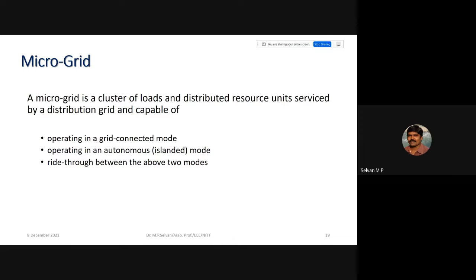A microgrid should be capable of operating in grid connected mode and in isolated or autonomous mode. If this capability is not there for the distributed resources in the distribution network, you cannot call it a microgrid. So if you have only grid following inverters, you cannot call it a microgrid, because they cannot form a microgrid. The inverters used should be capable of grid forming nature. If you go through articles on power electronics, you'll come across these two terms: grid following inverters and grid forming inverters.